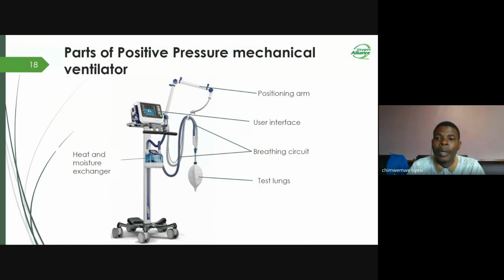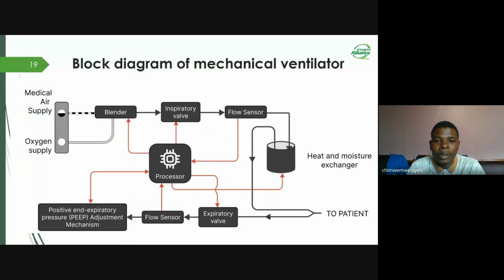Now, let's talk about the main parts and setup of a mechanical ventilator. So to start, a mechanical ventilator has a number of key components. A typical ventilator will have input ports for medical air and oxygen, a heat and moisture exchanger, some just call it a humidifier, a positioning arm, user interface, and also a breathing circuit, and of course a test lung. Moving on, I'll talk about the block diagram of the mechanical ventilator and how air moves from the ventilator into the patient and out of the patient into the ventilator or to a scavenging system.